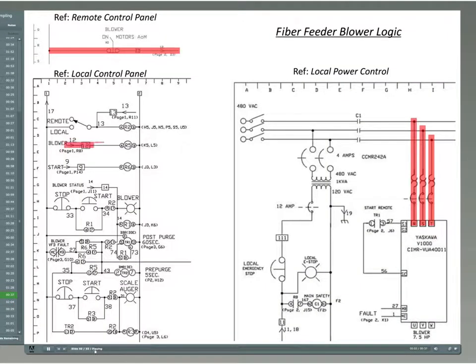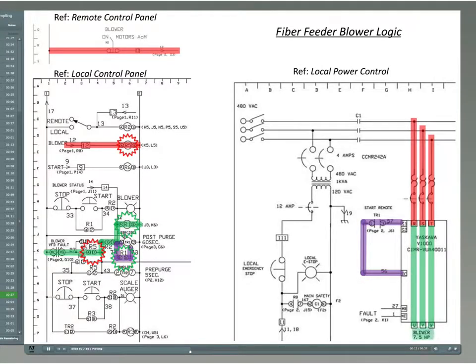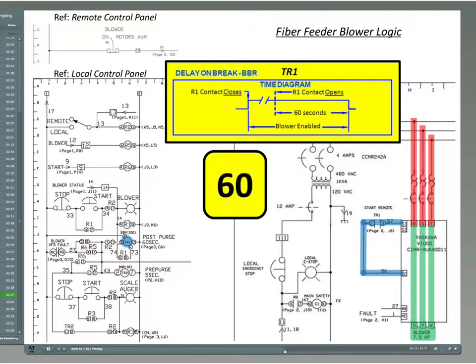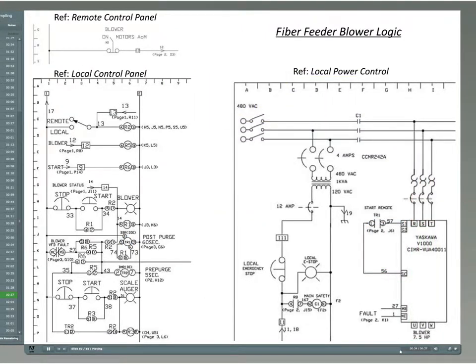On and off from the remote control panel without starting augers. This is designed so that the scale can be zeroed under process conditions and the airflow is up to full speed before the augers start. Otherwise, the fiber added by the augers will not be carried away in a slow-moving airstream. The blower is required to stay on after the augers are stopped and the flow of fiber has ceased. This is controlled by the post-purge timer. This added blower runtime is used to clear the line of all fiber before shutting the process down.